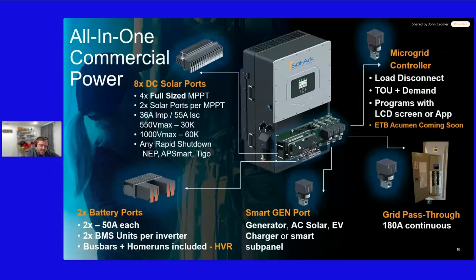The commercial inverters have 8 solar ports with 4 MPPT. All of the MPPT are full sized, so you don't have to think about whether one is larger than the others - they're all full size and well rated for amperage. They can accommodate bifacial solar paneling. The 30K goes up to a 550 volt design maximum, and the 60K is 1,000 volt.